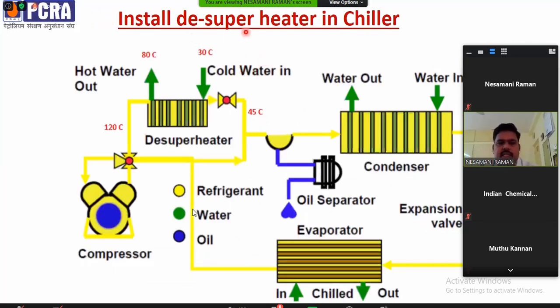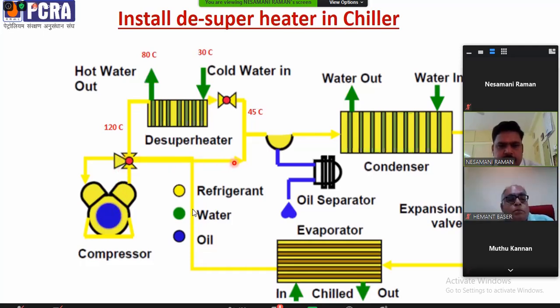So this is the schematic diagram of installing a desuperheater in a chiller. In the normal scenario, the compressor output refrigerant goes to an oil separator, because the compressor has an oil cooler for the bearings, and that oil gets mixed with the refrigerant and is carried along with it. We have to remove that oil using the oil separator. Otherwise, if the oil is carried with the refrigerant to the condenser, it will foul the condenser, so heat transfer will not be proper and we need to do maintenance frequently. So the suggested scenario is installing a desuperheater.